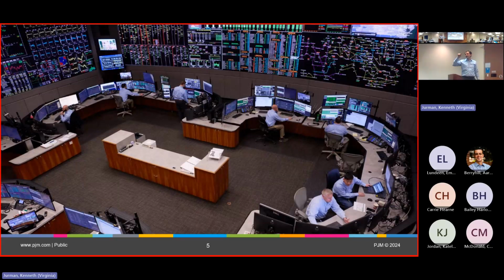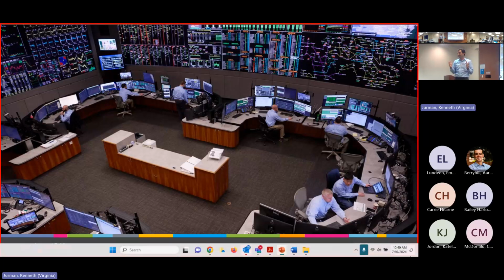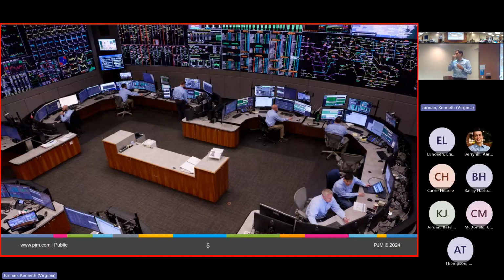So there's a little yellow dot in the very middle there, and that dot is constantly moving. If you stand in the control room, you can watch it—it just looks like a little squiggly thing moving around all the time. If it gets into one of those red areas, a clock starts, and we give ourselves 10 minutes to get it out. The operator will make decisions to get that yellow dot out of the red area. We're mandated to get it out in 15 minutes, so we give ourselves a 10-minute clock, which gives us a 5-minute buffer. We would technically get fined by our reliability regulator if it stayed in one of those red areas for longer than 15 minutes.